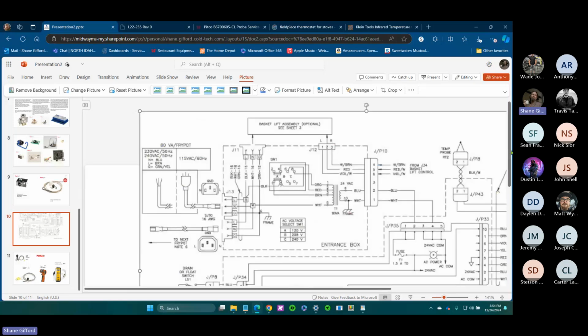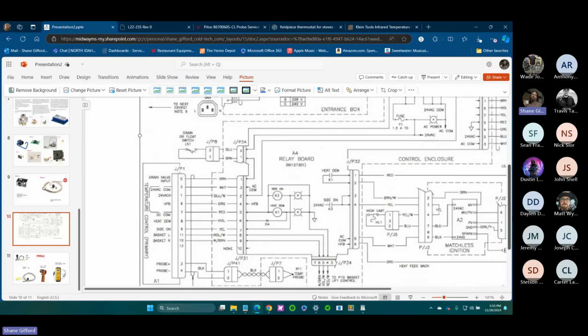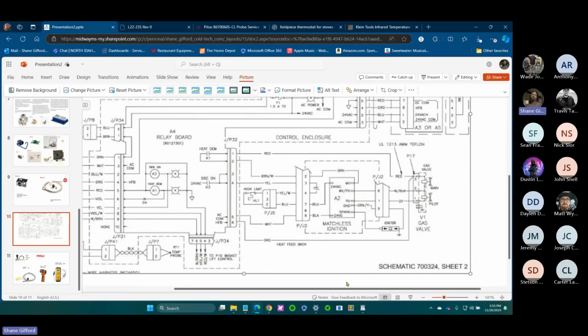And so when you're looking at your schematic, if you're having a hard time tracking down where some of these parts are, or maybe you're just not quite yet familiar with what part is what, like what's the name of that part, what's it do? A lot of times you can figure that out by looking at the schematic. And you can find this right here. This is jack and plug 2, and it's near the blue spark control board. And then there's your gas valve. So look in that area or look on the board and find where it pertains to this. And then you'll see, okay, if I test 1 to 3 right here and I've got 0 voltage, then chances are that limit's closed. If you do check voltage there and you've got 24, chances are that switch is open, or vice versa.